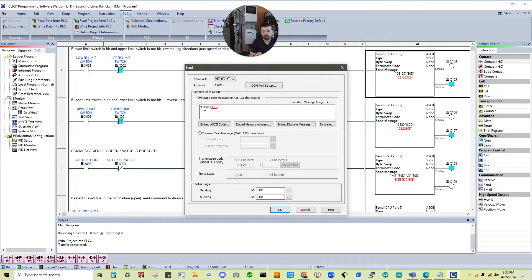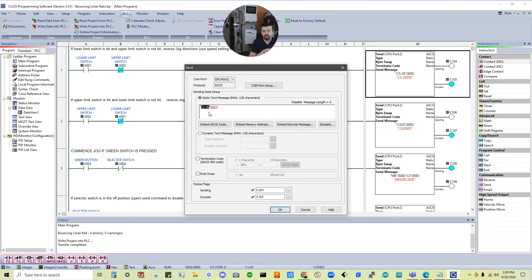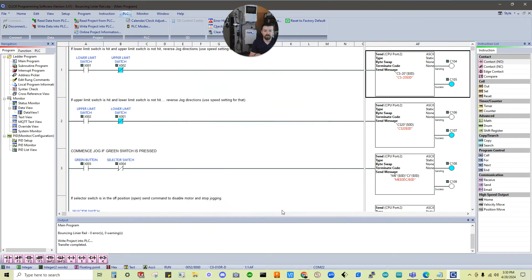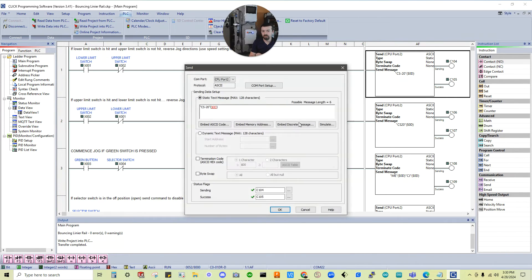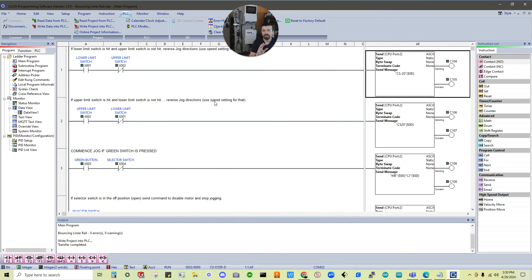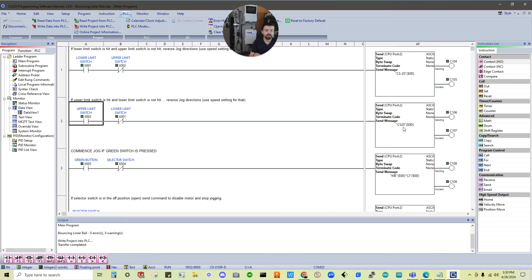And it's going to then write the static text. So that's how we're controlling the driver. We're outputting the static text for different command types. And I'll show some of that. So this one's a cs command. You can see cs negative 20. So what that is saying is change speed cs negative 20. So the speed of negative 20 will be now the updated speed. You see everything turned off there because I updated this even though I didn't make a change. Because I clicked okay. Now it's going to make me rewrite the project before I can do the status monitoring again.